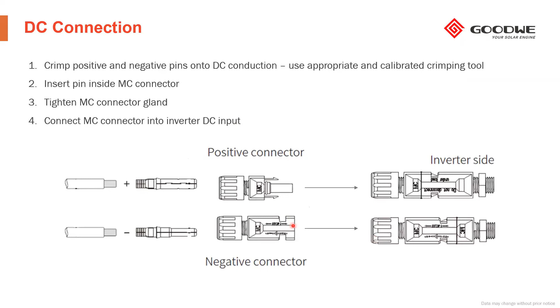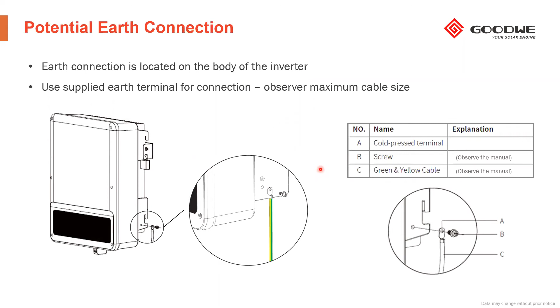Same for the DC connectors, and the potential earth connection. It's mandatory, from the protection point of view and also the operation point of view, that the inverter and the mass of the entire PV array be connected to the same ground. So please pay attention to this.